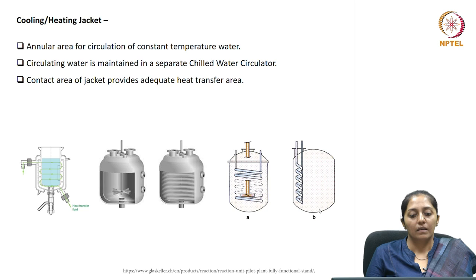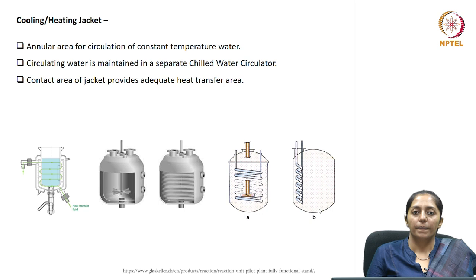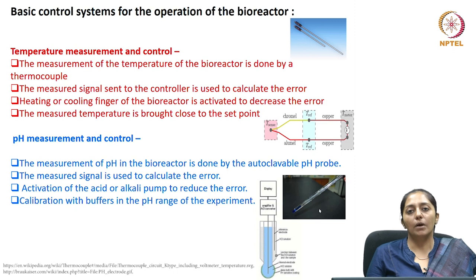The heating and cooling jacket arrangement involves an annular area of constant-temperature water. Depending on the size of the reactor, there are different arrangements: water from the chilling unit is circulated around the entire reactor body, or if the reactor volume is very small, heating or cooling fingers are inserted inside the reactor through which chilled water from the chilling unit is circulated to maintain the temperature of the liquid broth.